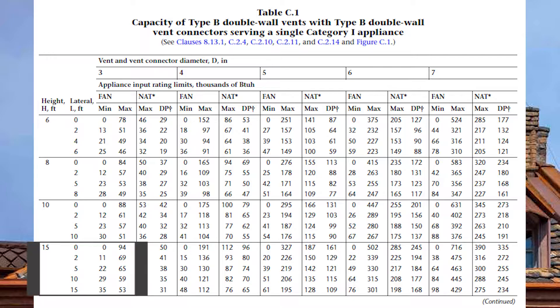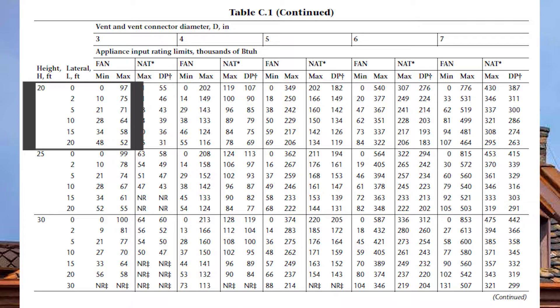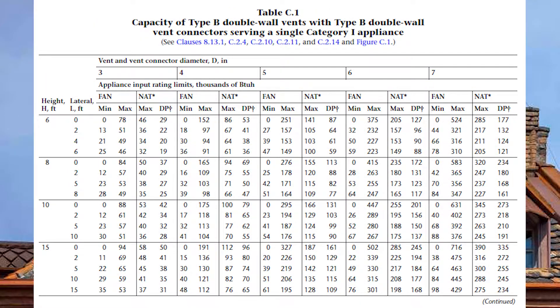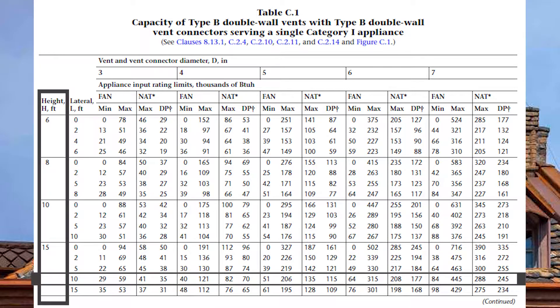There's a 15-foot and on the following page a 20-foot designation for vent height — no 18. So we need to do some math and thinking to find a table value in between. We come down to the 15-foot vent height, go across on the 10-foot lateral, and see if we can find something close to 125,000 BTUs in the fan max column.